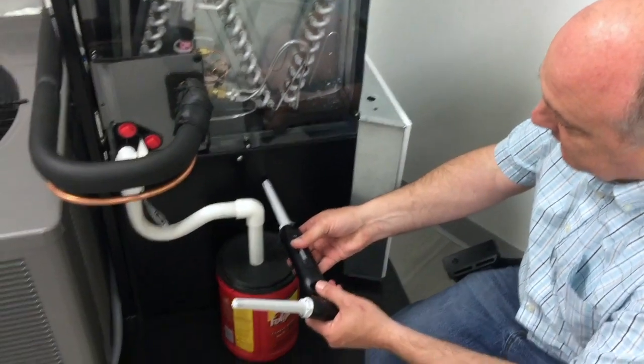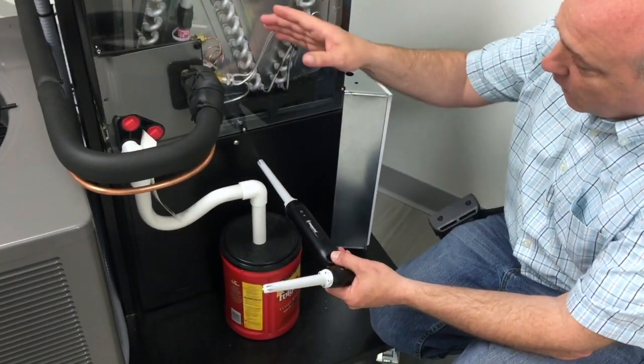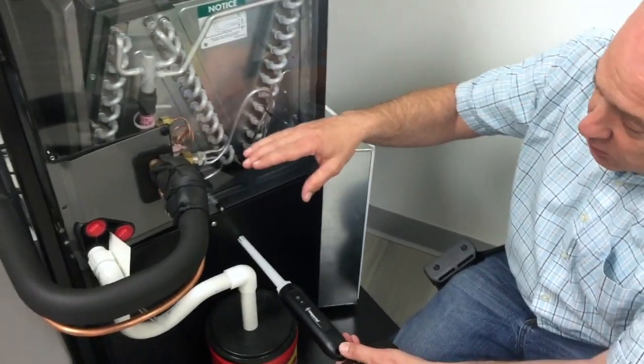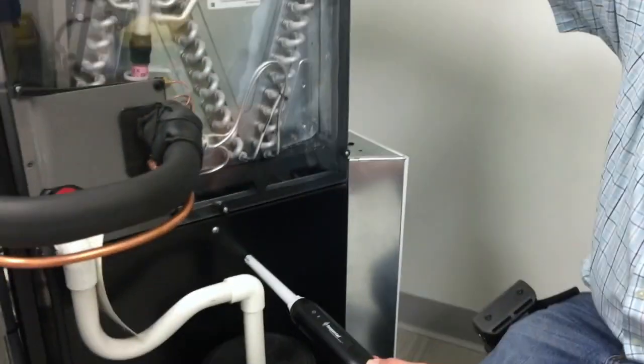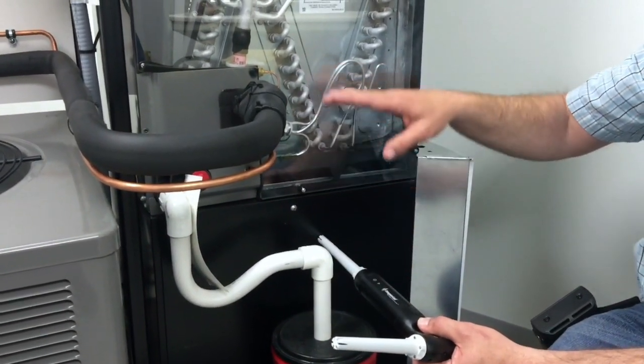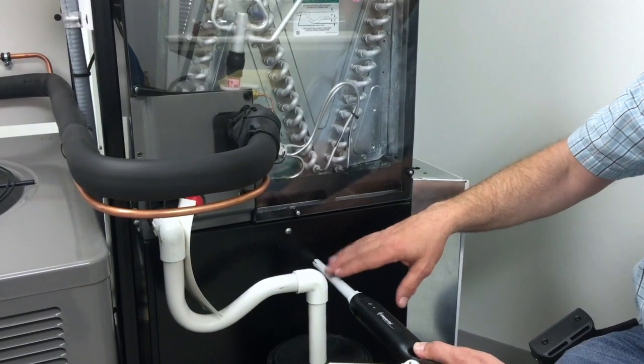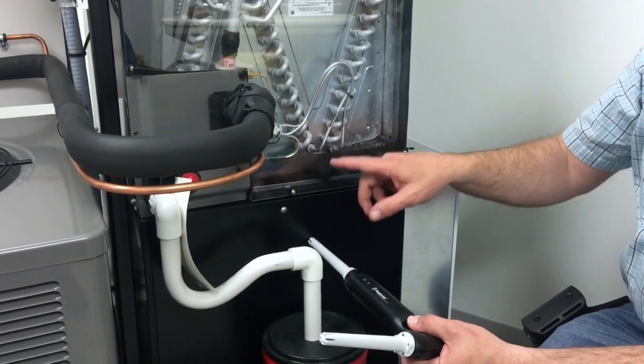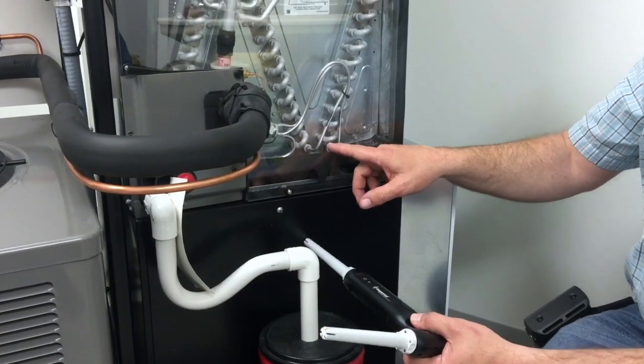We don't want to be down here in the bottom right below the coil. Heat travels from hot to cold and it's called radiant cooling. So even though the air is flowing up this direction, the probe will still get influenced by the cold evaporator coil. If the probe can see the coil, the temperature will be influenced. So we do not want to be directly below the evaporator coil.